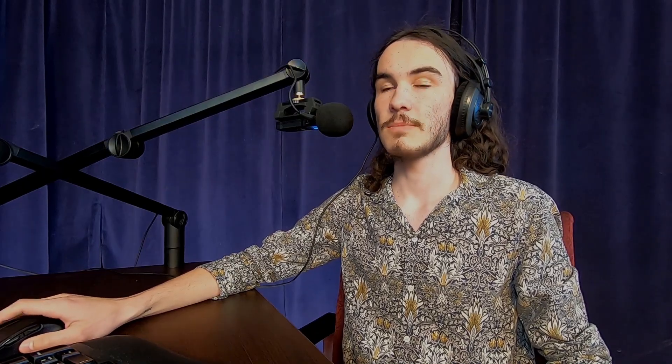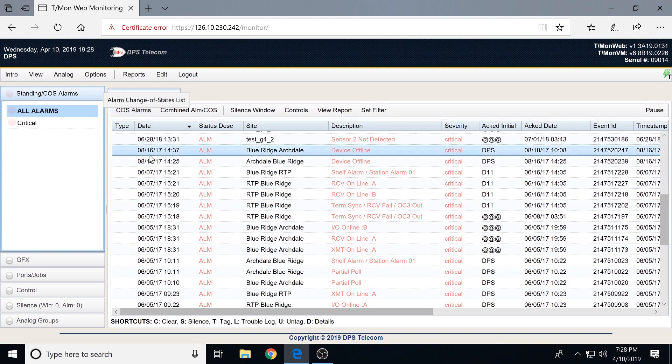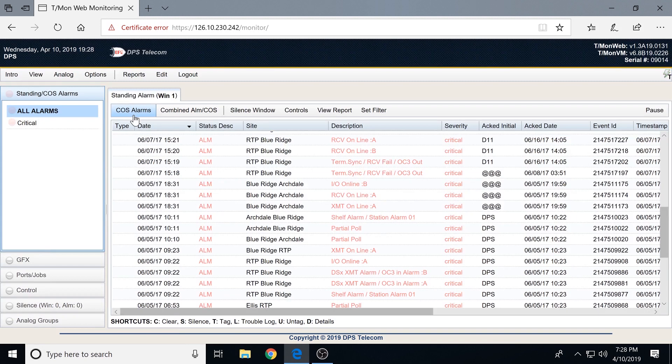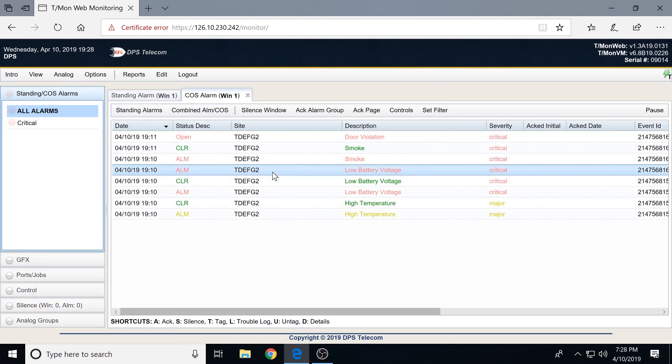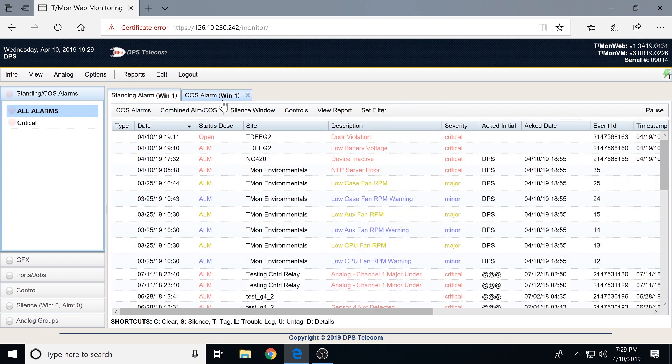We're looking at a lot of points that have come into the system. Right here we have our standing alarms — all alarms currently active in the system. We also have COSs, which are change of states. These are a historical view of all your points and their transitions between alarm and clear, whereas standing alarms shows just what's currently in alarm. A standing alarm is for quickly getting to current unresolved issues, whereas COS shows both what's currently standing and a historical view. COSs never go away — they're a record of what happened, say, in the middle of the night when you get in in the morning.